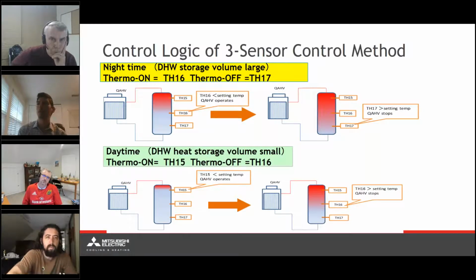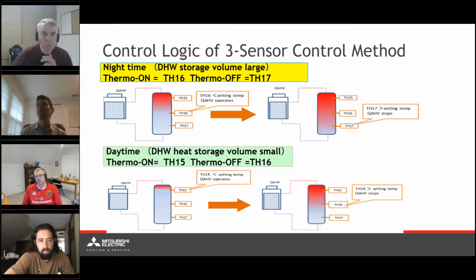So for daytime operation, we're not going to be cycling the QAHV on until the topmost water temperature sensor dips below that setting temp. And we're going to run that system until the middle water temperature sensor achieves that setting temp, at which point the QAHV will turn off.